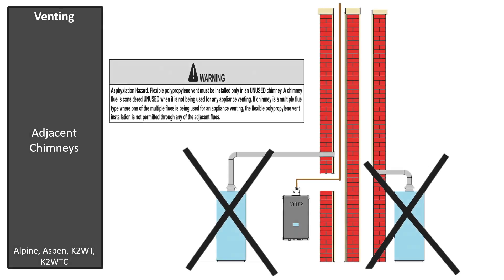In closing, when the building has a multiple flue chimney, you may not use any type of plastic, including polypropylene pipe. Stainless steel is required.